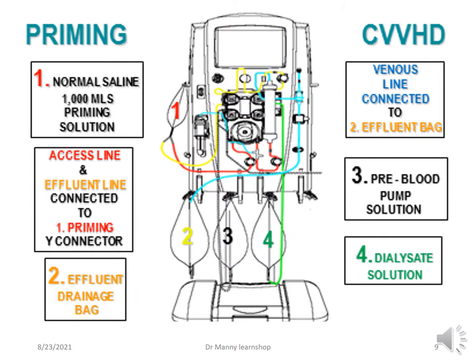So when it comes to priming, again, similar, but now we have a dialysate solution, not a replacement solution. So normal saline is the priming solution. It's connected to the access line and the effluent line via the priming Y connector, and it drains into the effluent drainage bag. The venous line is connected to the effluent bag. The pre-blood pump solution is also connected, 3, and there is a dialysate solution. It primes the whole circuit.